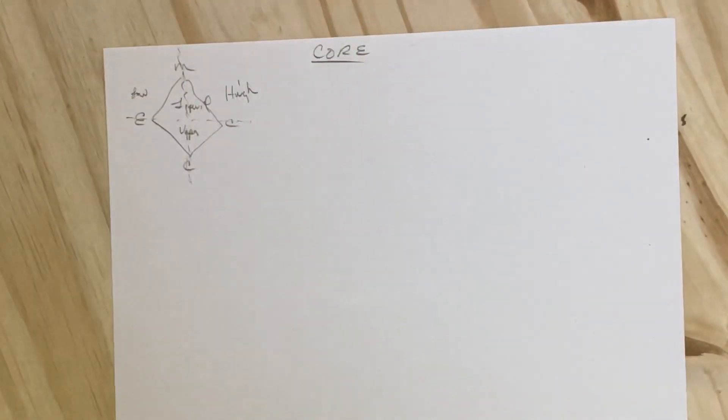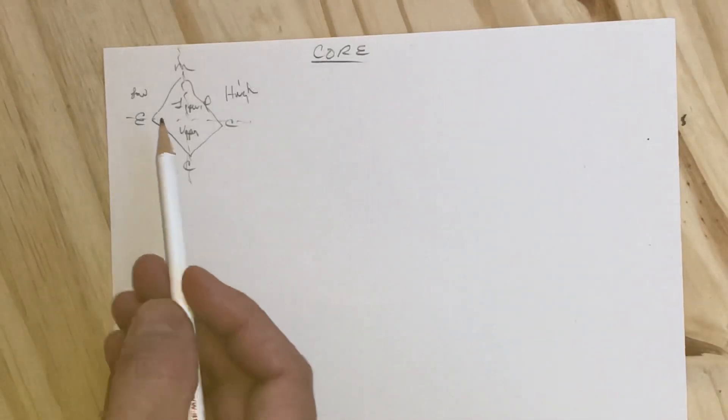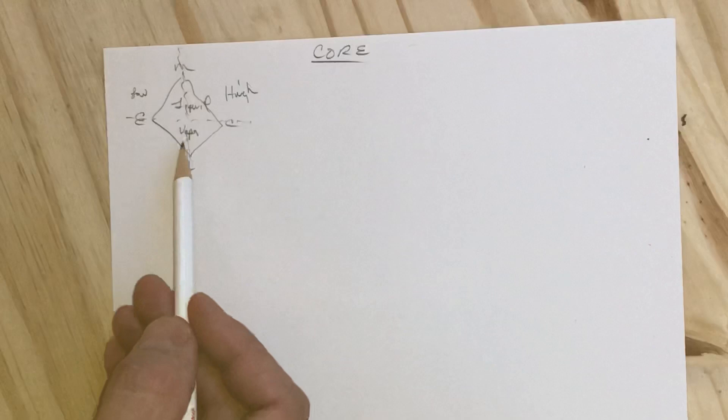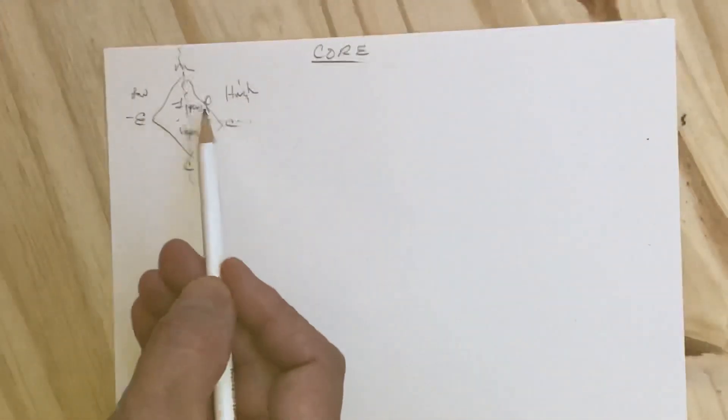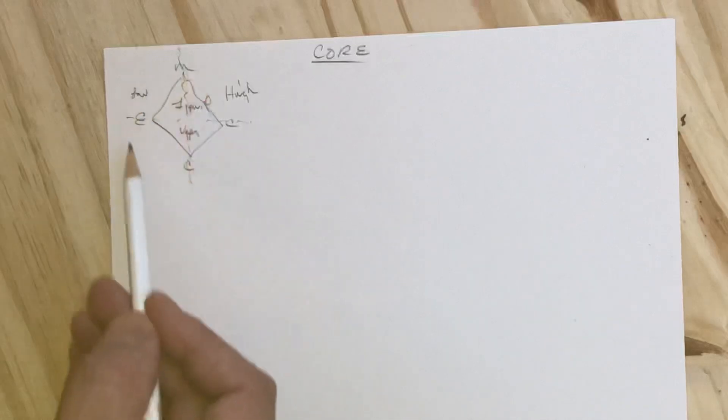With this diagram, if they ask you the state and condition of the refrigerant leaving the evaporator and entering the compressor, you can see it's a low-pressure vapor, and that vapor is superheated because subcooling happens at the condenser.